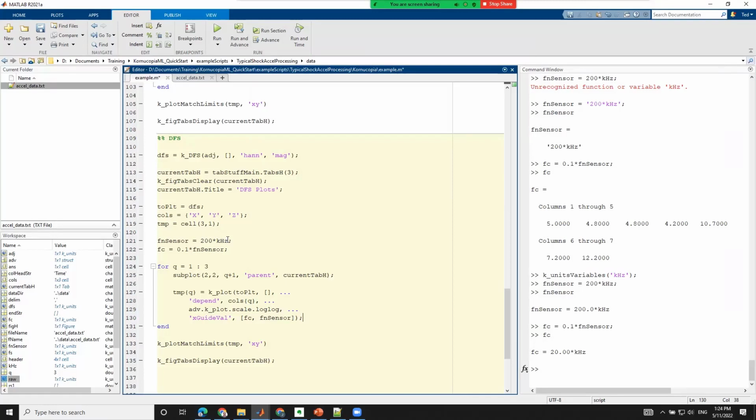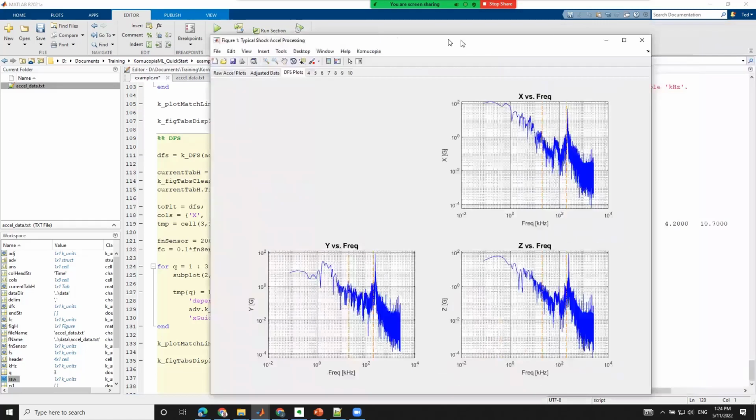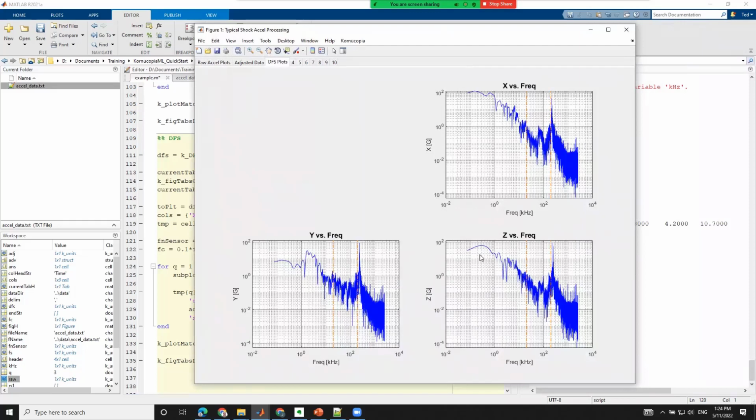And this value here is a value we are getting from a data sheet. It's not exactly the one for our specific sensor. It's an approximation. Let's see how good the approximation was. So we have 3 instances of this sensor, and their resonance are pretty close to the nominal data sheet number of what the resonance normally is. And 1/10 is down here, which is where we're going to set our cutoff frequency when we do a filter on the data. And we will filter away the resonance.